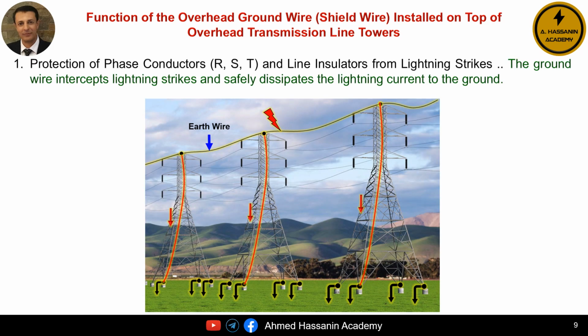The first function of the earth conductor, shield wire, or ground wire is to protect the phase conductors and also the insulators of the overhead line from direct exposure to lightning strikes. Naturally, the earth conductor or shield wire receives the lightning strike because it is the highest point on the overhead transmission line and works to divert and discharge this lightning strike to the ground through the grounded metallic tower structure.